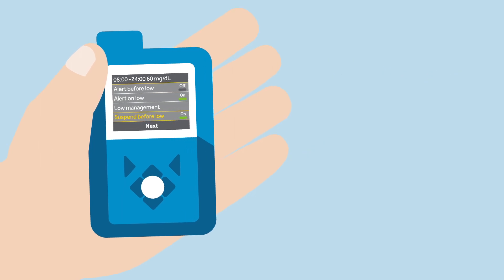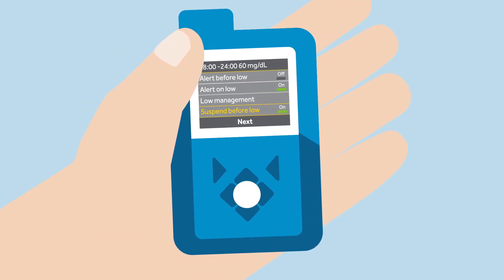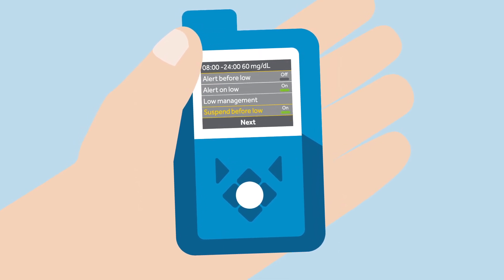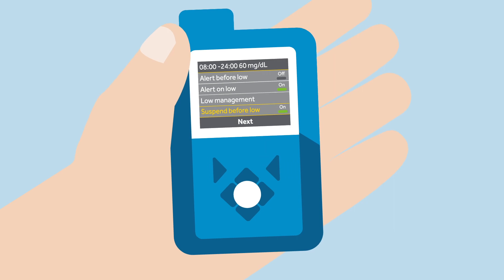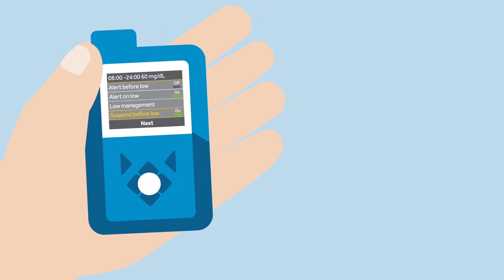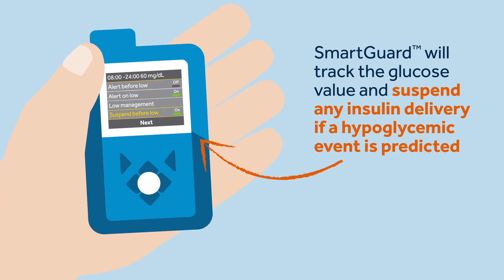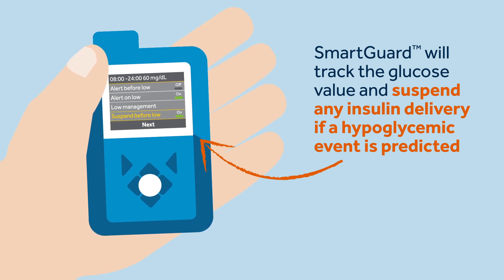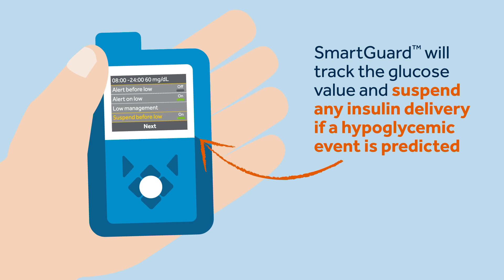Kelly also told Sophie that when she uses manual mode, she must remember to activate the smart guard suspend before low feature to protect herself from hypoglycemia. Sophie must confirm this alert by pressing OK. This feature means that smart guard will track the glucose value and will suspend any insulin delivery if a hypoglycemic event is predicted to happen within the next 30 minutes.